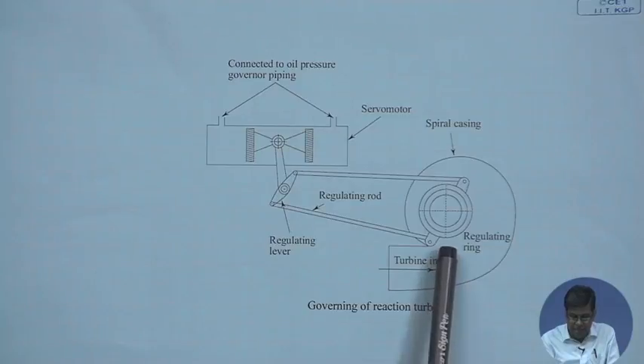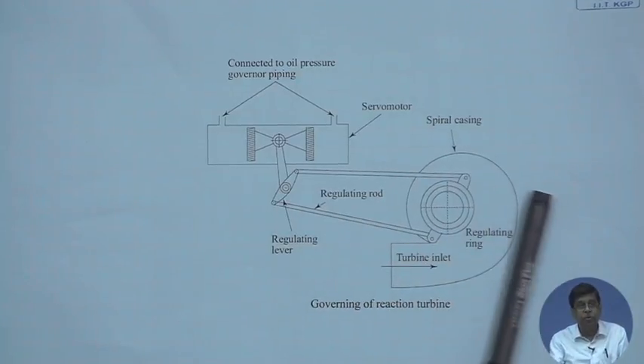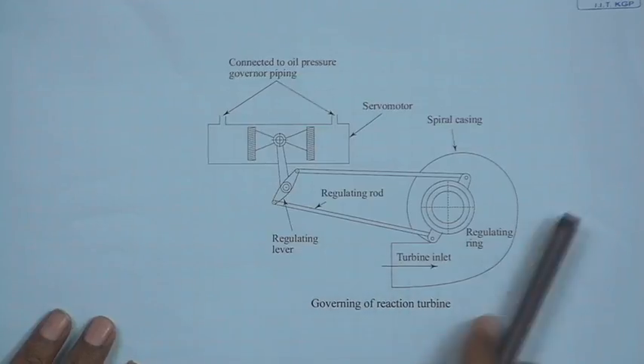Apart from the wicket gate mechanism, there is another mechanism acting in parallel — a relief valve or pressure regulator in the main line. This diverts water another way, not allowing it to reach the turbine inlet. It is similar in concept to deflector vanes used in Pelton turbines, which deflect the jet away from the runner before it reaches the turbine, so the water goes a different way and cannot reach the turbine. The pressure regulator or relief valve does the same thing in reaction turbines.